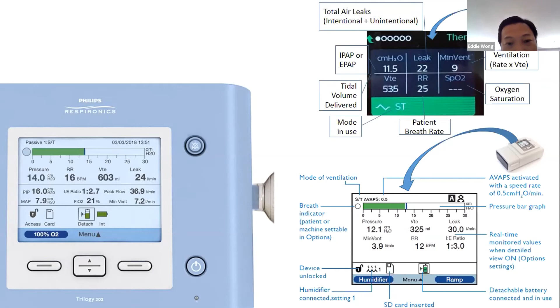What I call the actual tidal volume, number 1, VTE. Number 2 is the respiratory rate, RR. Number 3 is the minute ventilation, min ven. Number 4 is the leaks. It depends on the model of ventilator you use. If you look at the top right here, this is a simple BiPAP. You see the VTE here, 535. RR is here, 25. Minute ventilation is here, 9 liters per minute. Leak is here, 22 liters per minute.